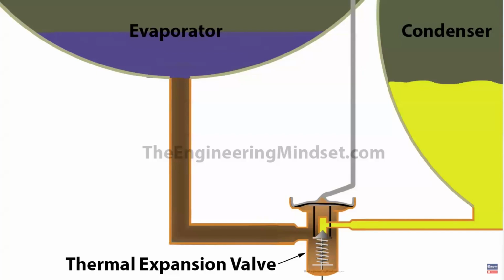control. So the thermal expansion valve is very similar to the pilot operated one, except that it hasn't got the main expansion valve there. The thermal expansion valve is the main valve in this type. So again, we've got the capillary tube rising up and connecting onto the suction line to measure the superheat. And we've got the refrigerant in the condenser, which will flow through, is being held back currently by the valve head. And once released, that will flow then off into the evaporator. So the pressure is starting to build in the capillary tube due to the superheat transferring its thermal energy over into the thermal bulb and expanding that refrigerant. That pressure increasing and pushing down the diaphragm, which pushes down on the pins and starts to knock the valve body off of its position, allowing some refrigerant to start flowing from the condenser and into the main valve. That refrigerant then starts to flow and goes off into the evaporator.